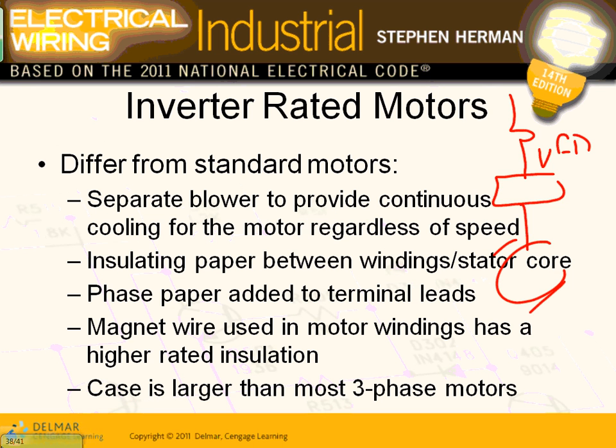Your VFD, guys, in order to drive a motor, and these are induction motors, speed controls the motor. First of all, you can ramp up the motor, ramp it down, so less mechanical and electrical stress in the system, and speed control it. In order to do that, guys, you need to do the following. First of all, in some of them, they use a separate blower to cool the motor. They need to be able to cool that machine.